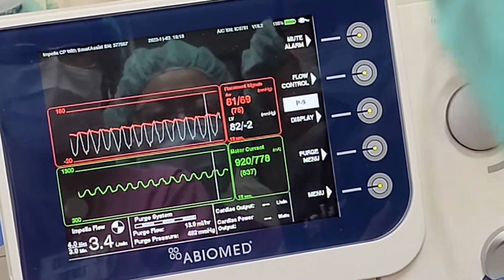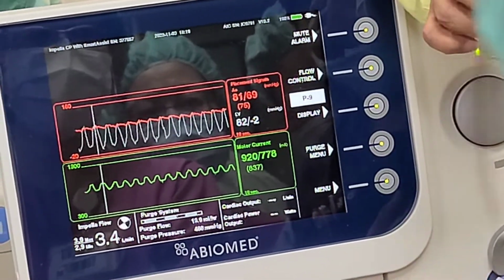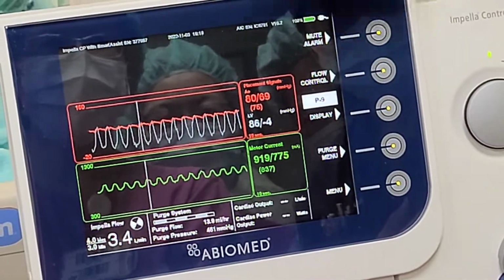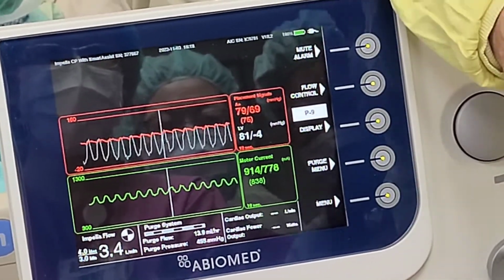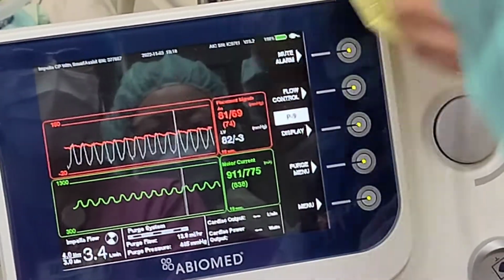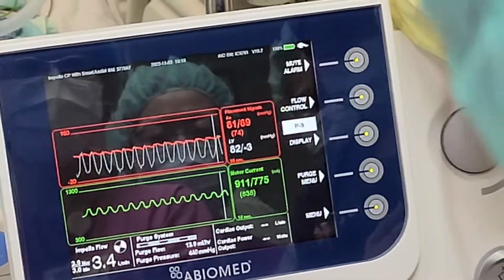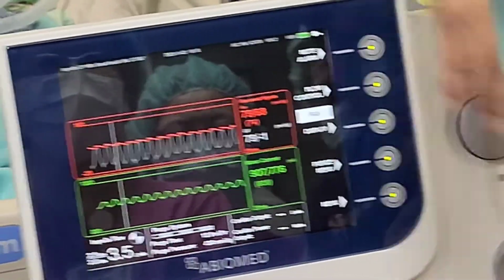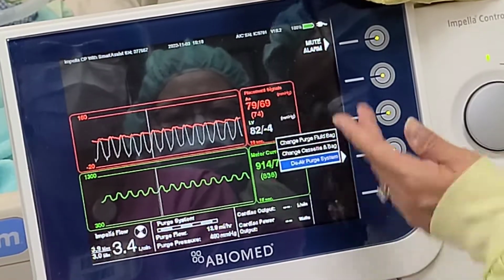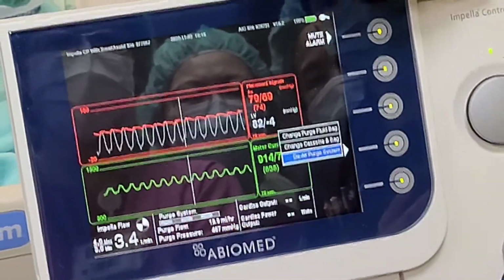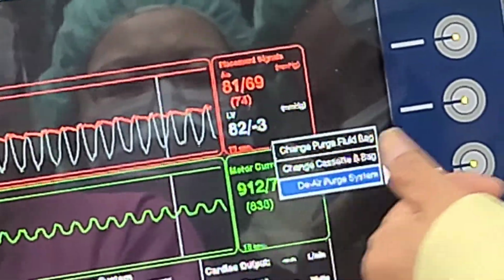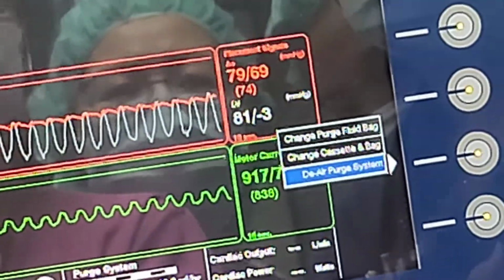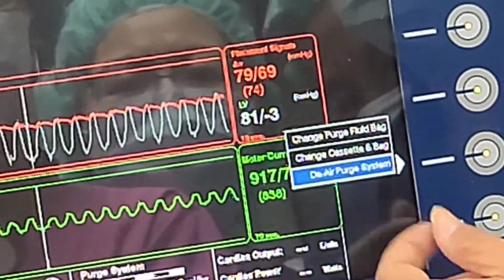Purge - you remember the side arm I mentioned, the dextrose that goes in to make that barrier so that the blood doesn't enter into the motor housing? That's purge. So the purge menu gives you a few options: you can change your purge fluid bag, meaning you change this bag, or change cassette and bag. The cassette is inside here, I'm going to show you the cassette.